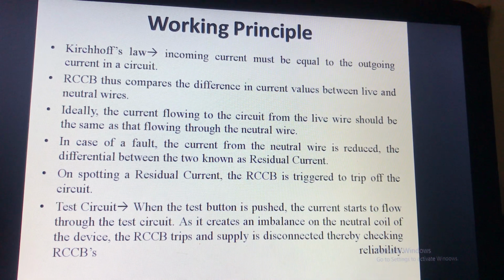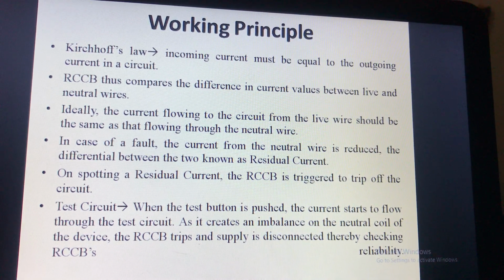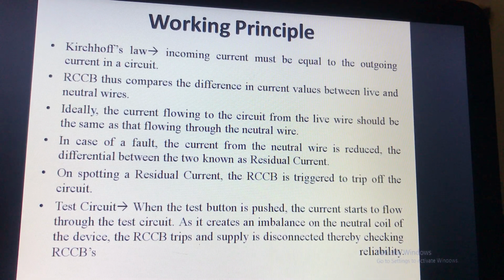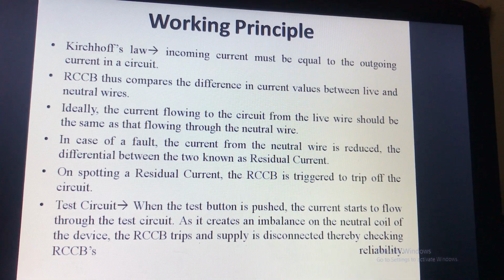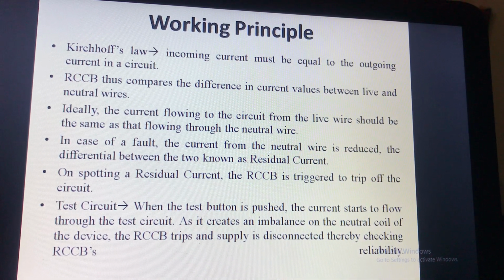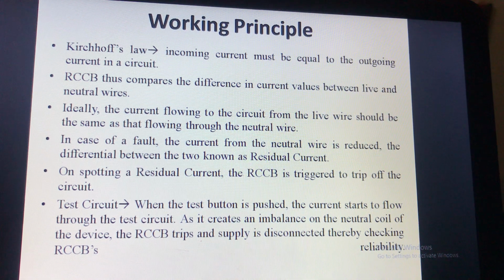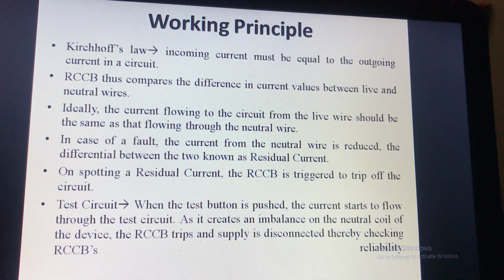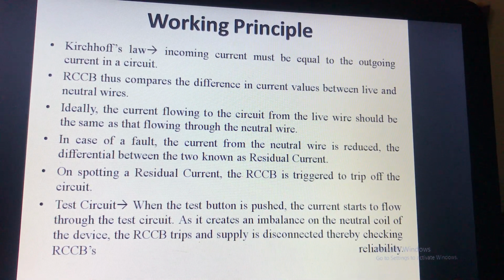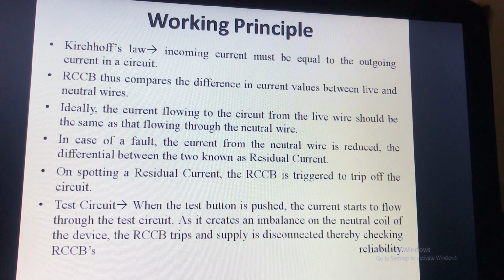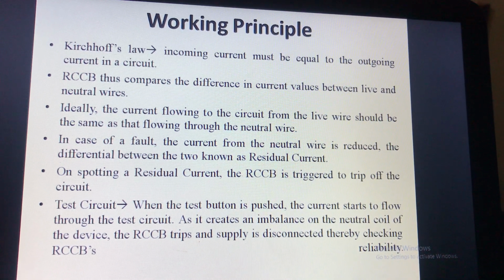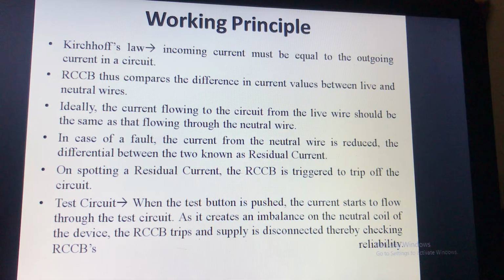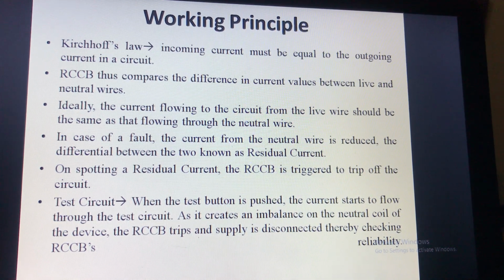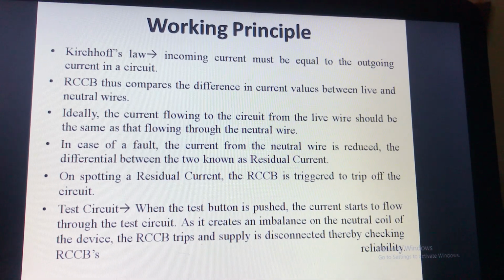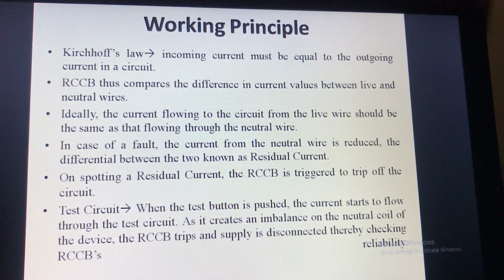So the test circuit is there to ensure the reliability of RCCB. There is a test button which is provided on RCCB. If we want to check the working of RCCB, we just push that button. By pushing that button, the RCCB must get operated. If it is not operated by pushing that push test button, then checking of RCCB is required.